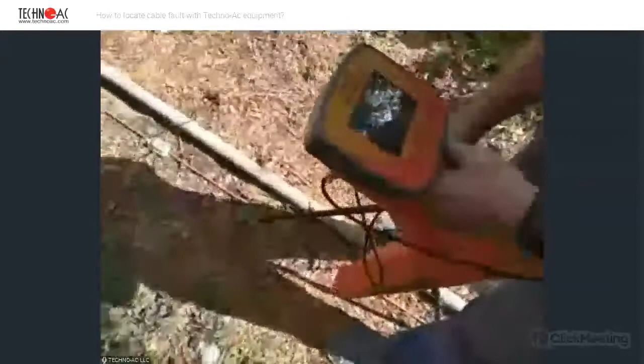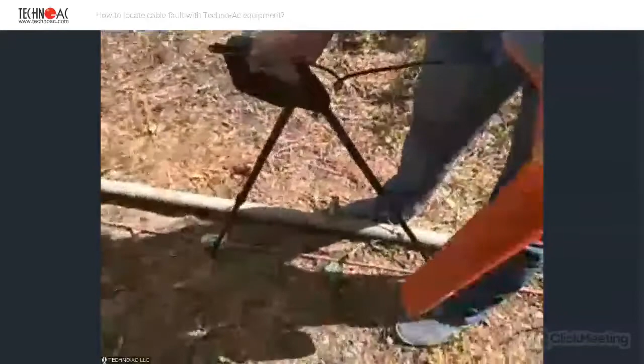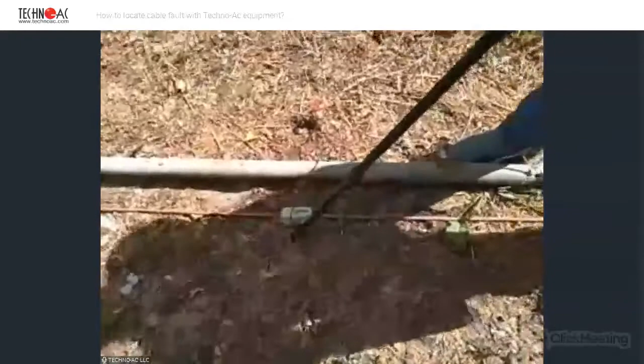So now I'm 1 meter away from the fault, and actually I have my signal overloaded. You can see this icon here, and it means that the signal is overloaded, and our graph is also full. And now I'm placing one leg of the sensor close to the fault and another one 1 meter away from it, and you can see that the signal a little bit changed. So this is the maximum signal, and here the signal has decreased. And see what will happen when I place the sensor right above the fault.